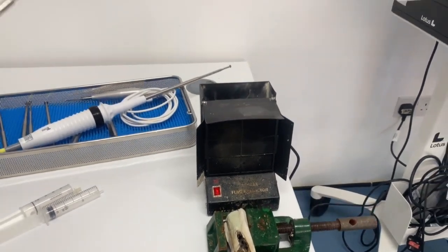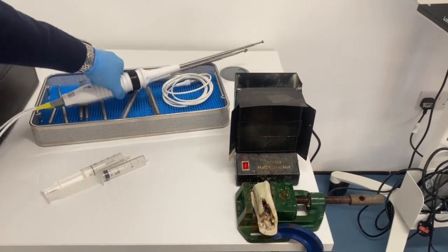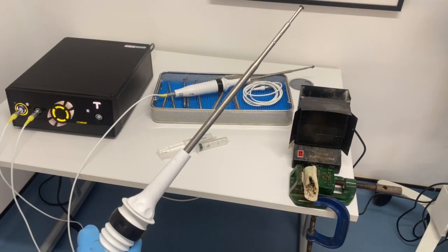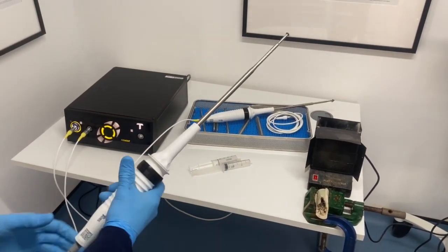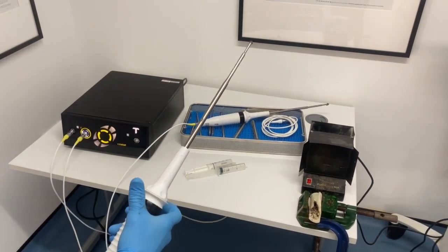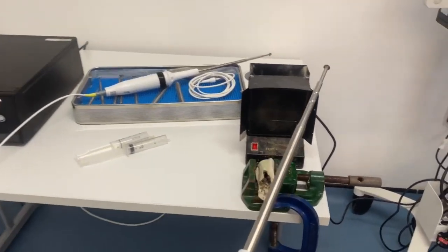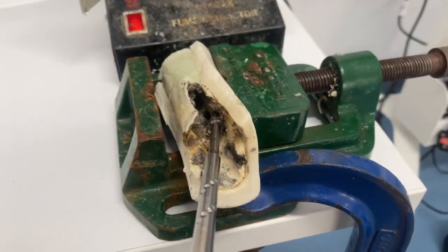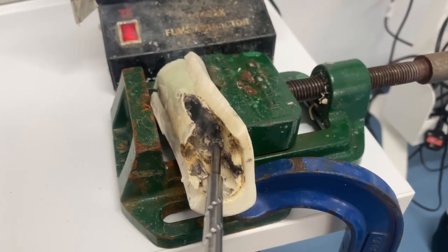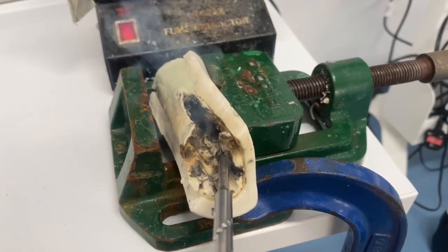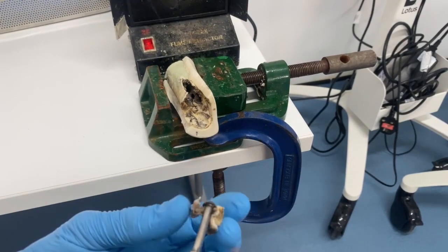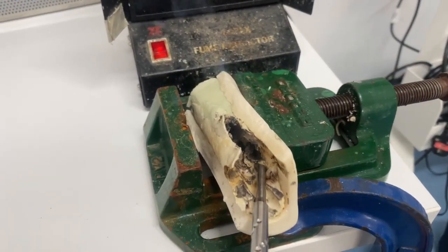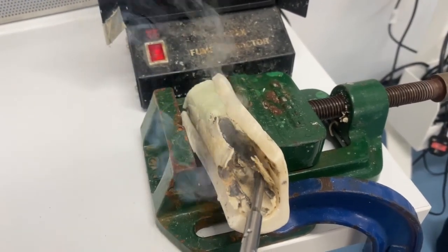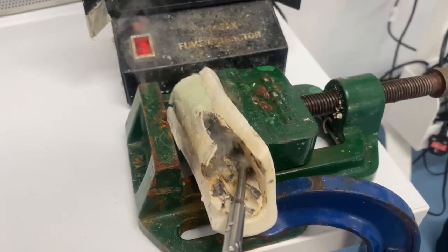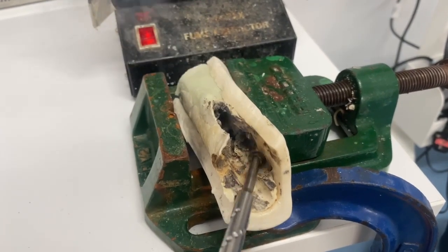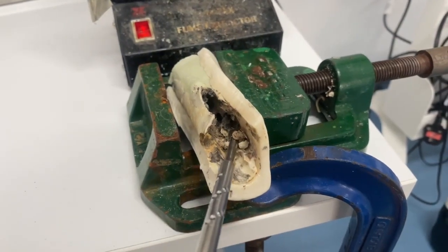Now we've got a section of bone here which will work very well to demonstrate the scraper. So I'll pick up the other transducer already fitted with the scraper probe. Now if I press the switch on this handpiece, it selects the other channel, so it's connected into 2, and then we straight away move into cement scraping now. This obviously works by pulling back, peeling back a big slug of softened cement, which can be plucked off, and in you go again. And again, you hear the screeching when the probe contacts the bone.